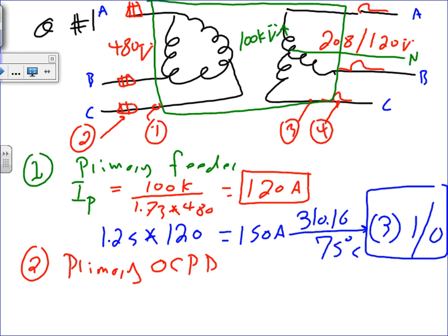For the primary overcurrent protection device, you take the 120 and you need to go to the table. Now both of them are less than 600, so which table am I going to go to? 450.3, A or B? B. If you go to 450.3(B), what's my multiplier on the primary side? 120 times 2.5. Are you guys there? The 2.5 is on the primary side. Remember, we're going to B because both of them are less than 600.